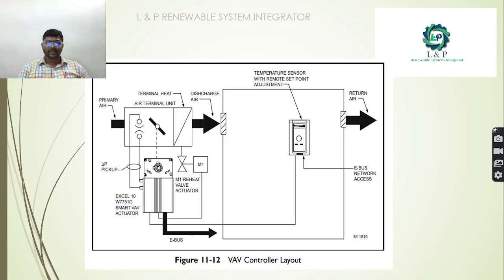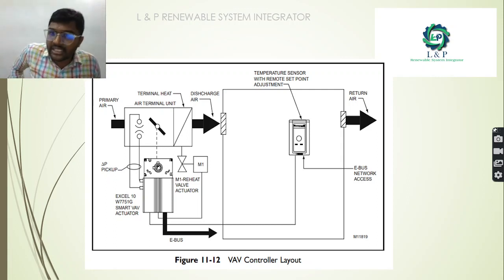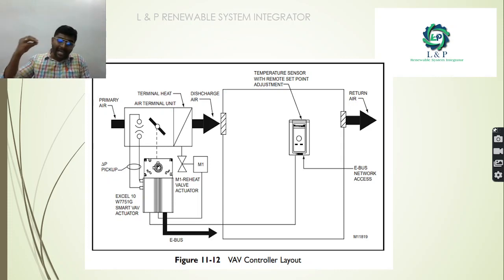Okay, so this is a VAV controller layout. As you can see here, this is a terminal unit. Okay, we have VAV actuators, so it is the work of the actuator to open and close the dampers. We also have the temperature sensors to measure the temperature. You also have the set point adjustments in the temperature sensor. Based on that set point, it will command the valve actuators, especially the damper actuators, to operate.